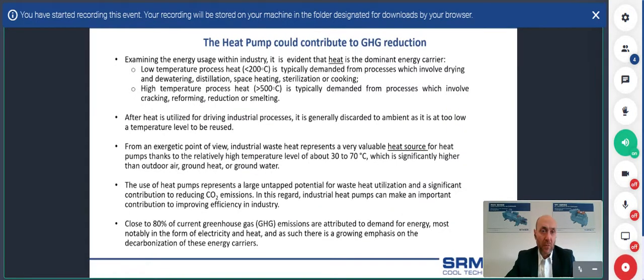So when we start to evaluate heat pump usage, we also have to investigate the applications. Normally we speak of applications at the industrial level, and industrial processes need different levels of heat. We can define low temperature processes, with temperatures lower than 200 degrees C, typically demanded for processes like drying and dewatering, or high temperature process heat, with temperatures above 500 degrees C, which normally involves cracking, reforming, and reduction.